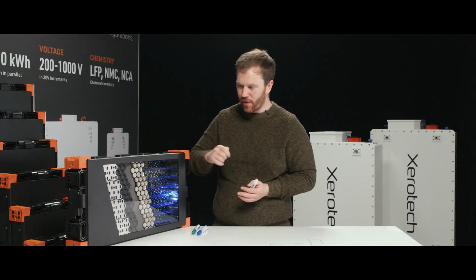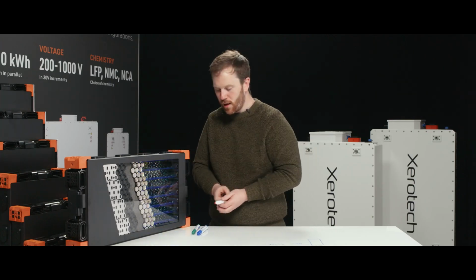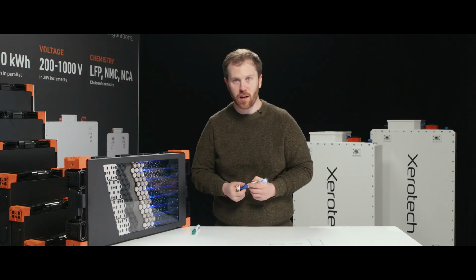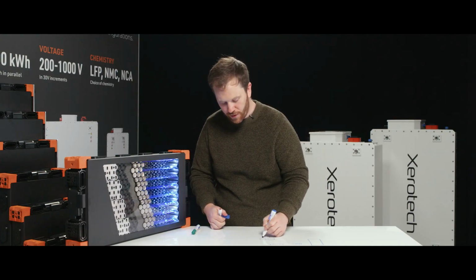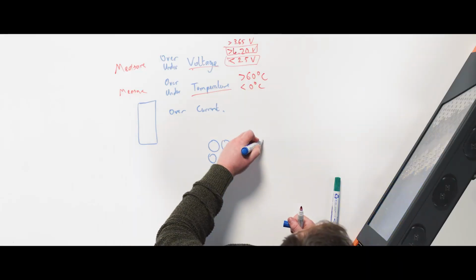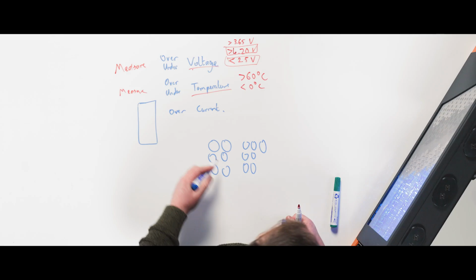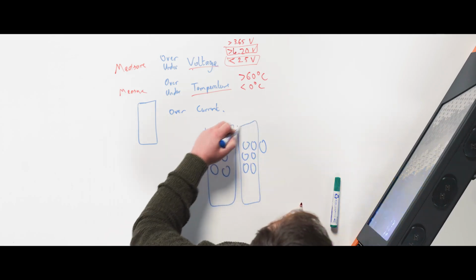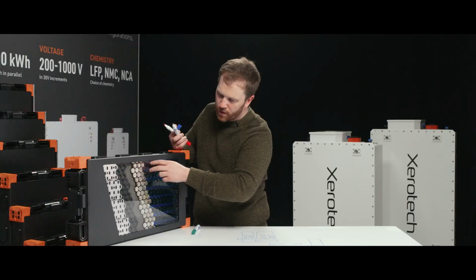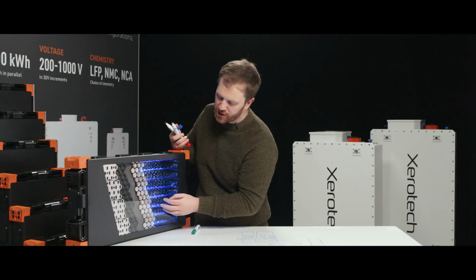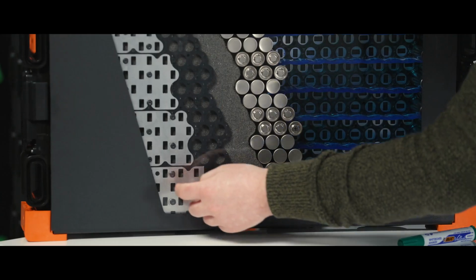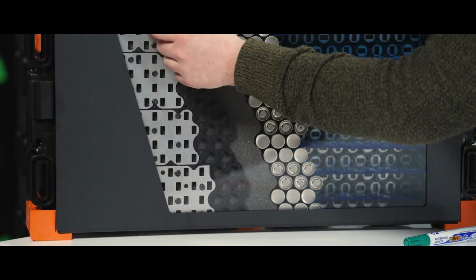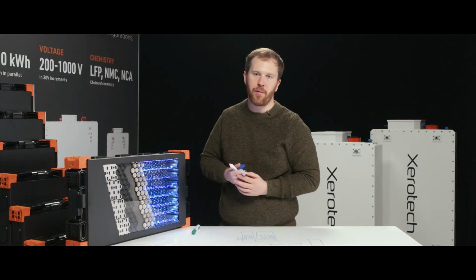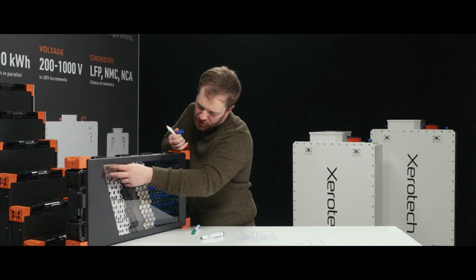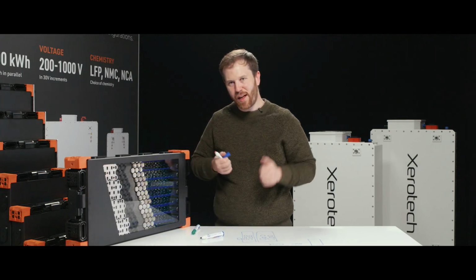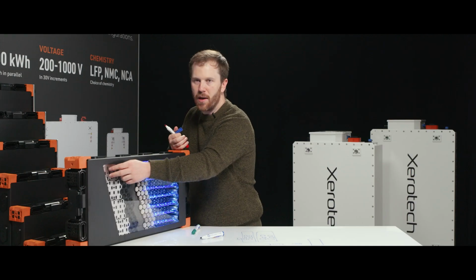An important thing to understand is that you don't have to measure each individual cell. You only have to measure all the same cells in a string. And what that means is, if we've got a bunch of different battery cells here on different groups, what matters is the bus bar, because if they are electrically connected on the same bus bar, they're all at the same voltage. So for example, on this module, you would need a voltage sense point touching this bus bar, this one, and obviously the corresponding ones on the opposite side, because every single battery cell that's on this bus bar is all at exactly the same voltage. So you only need to measure the bus bar.